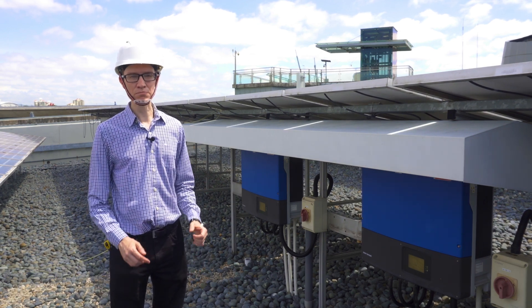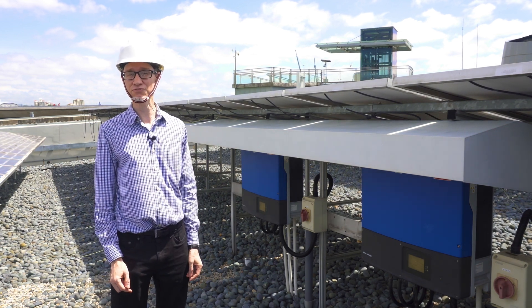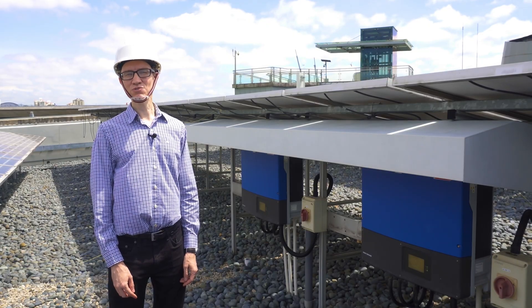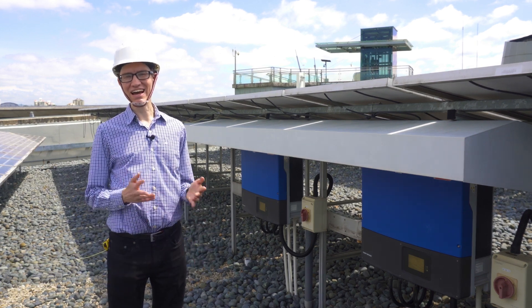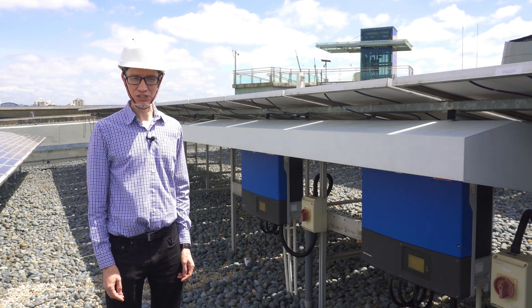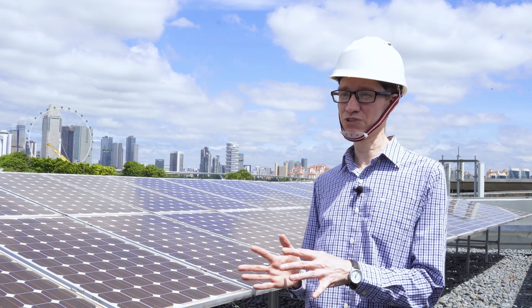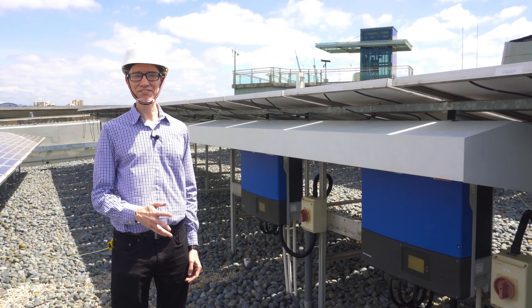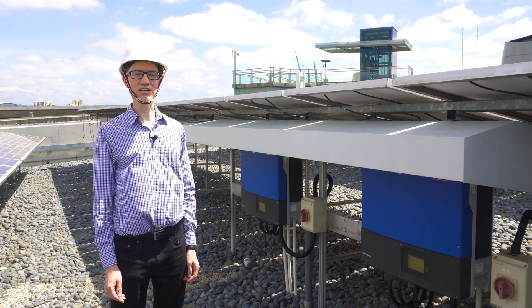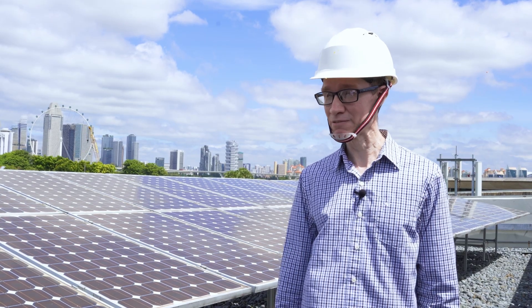But if the percentage of solar power as a fraction of the total generation capacity in Singapore were to increase in the future, there could hypothetically be problems with grid stability. There are various ways to solve that problem. The easiest way is to have gas turbines, which can quickly power up and compensate for any shortfall. Another option is to look into ways the grid could store electricity produced when it's sunny and then release that power when it's not. This remains a big challenge because of the costs associated with batteries and other types of energy storage, and because the amount of storage needed is so large.